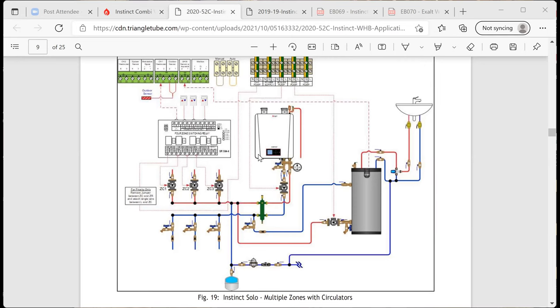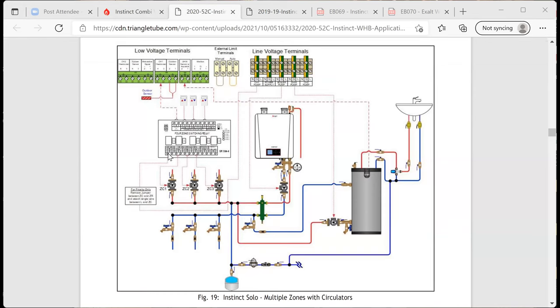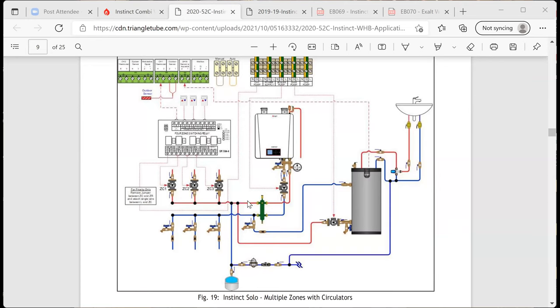So one thing is, if this calls, this indirect, how do we shut off these other zones? So what you do is, because we have this zone controller, all these pumps are going here. Our CH pump is not being used. So we take the L connection and we run it to VC on the control and remove the VR VC jumper. That way, when our tank calls, it sends power out to CH1, which disables these zones and these pumps stop working. That's one thing to note because a couple manufacturers out there can't do that. So it gives us true priority on that tank when we're using an auxiliary control.